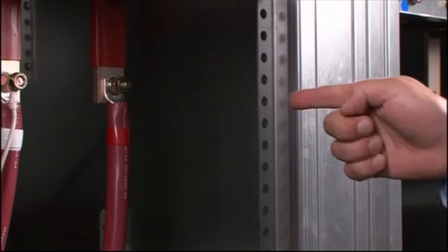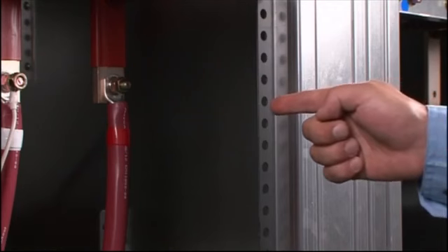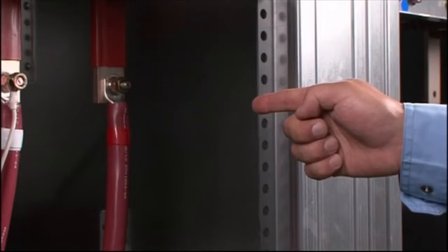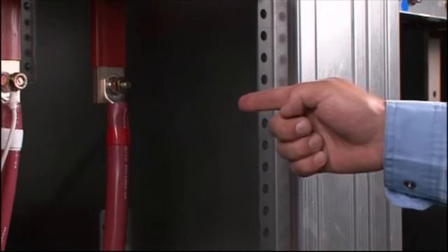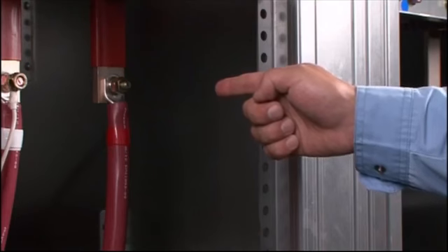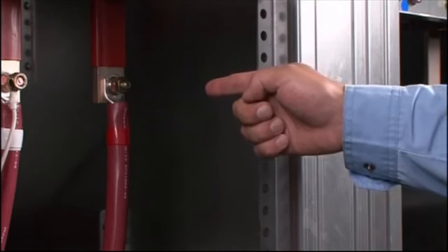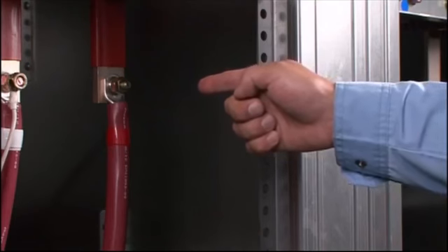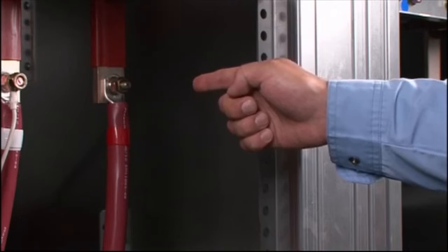Modern ships often use voltages as high as 6,600 volts. You are at risk of electric shock if you approach within 150 millimeters of a hotline of this voltage. The danger gap is approximately 20 millimeters for lower voltages.